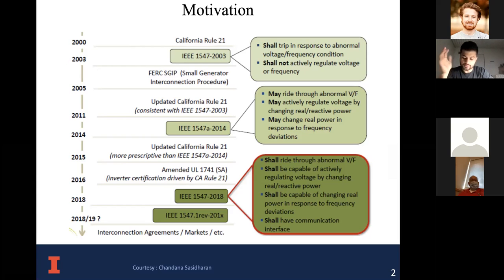So in that case, you still needed a standard, but what they did was they came up with a standard which says, in case of any disturbances on the voltage or frequency side, the DR would just trip. So it was: shall trip in response to abnormal voltage and frequency conditions, and it shall not actively regulate voltage or frequency. Which kind of makes sense, because if you think about it, there's not much DR. So even if you just trip off some DRs, it'll actually be good because the DRs won't get damaged, and the inverters won't get burned. So everything is fine. And even if it goes off, it won't affect the grid much, since the DR penetration is so little, it doesn't really matter even if you trip them off, right?